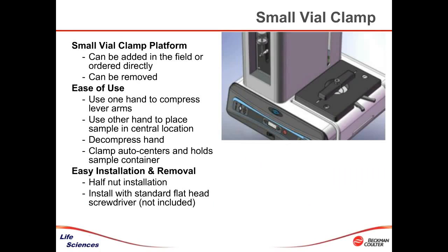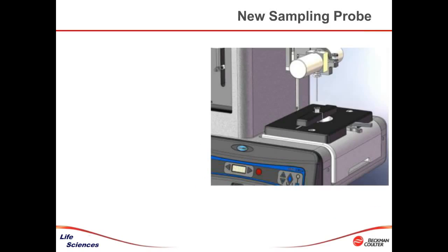In terms of dealing with proteins, some of the modifications that have been put into place are ways to deal with very, very small volumes, or maybe even material in a centrifuge or pointed tube, something that's kind of hard to balance on a flat stand. So in order to make that more effective, we've designed into the instrument ways to handle very, very small vials. And also, in terms of working with that, to be able to work with the minimum amounts, the 0.2 milliliters.